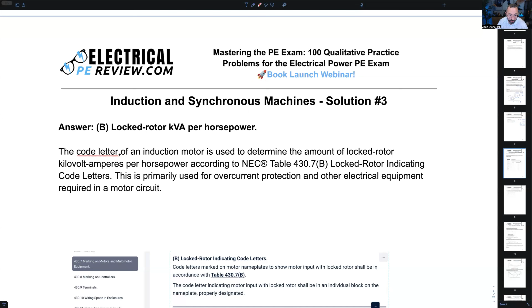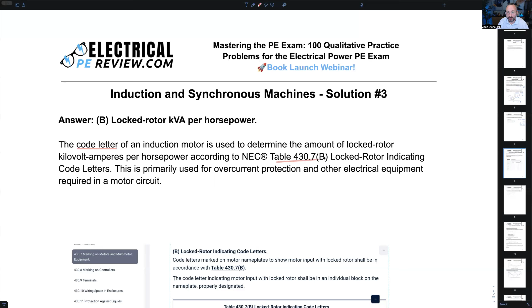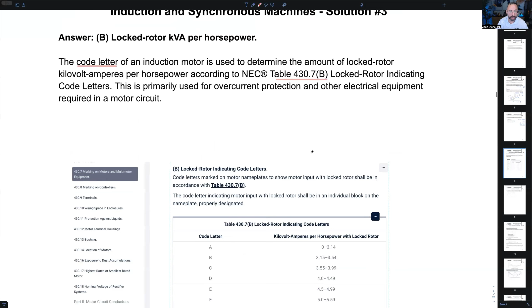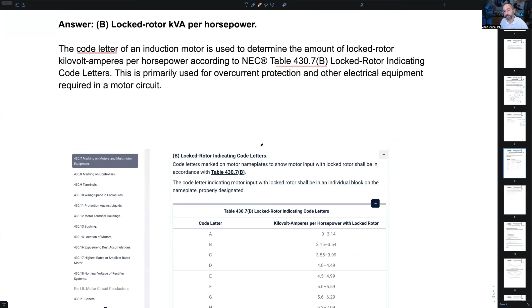The code letter, not to be confused with design letter, is how we look up in the National Electrical Code, table 430.7(B), the locked rotor information. So I pulled this up right before we started. I use the NFPA link. If you don't use it, it's a great resource. I think it's like 14 bucks a month. You can access just about every code that's on the PE exam except for the NESC, I believe. But anyways, here's the 2017 NEC, because that's what they're still testing on, 2017.